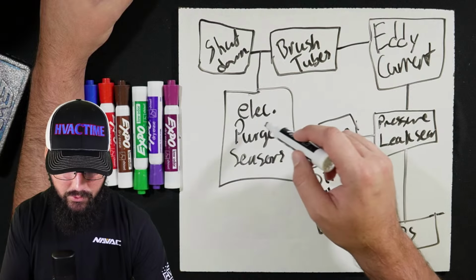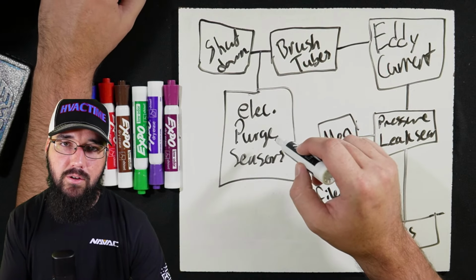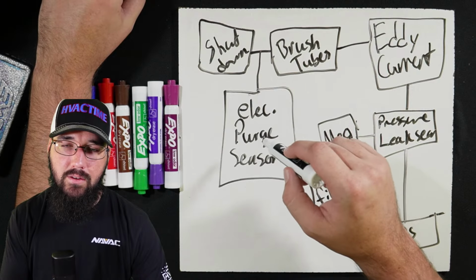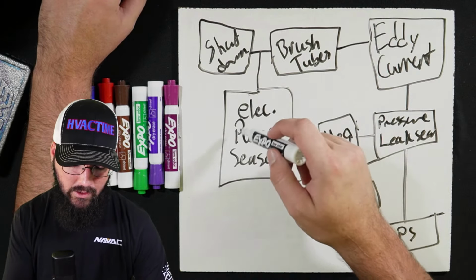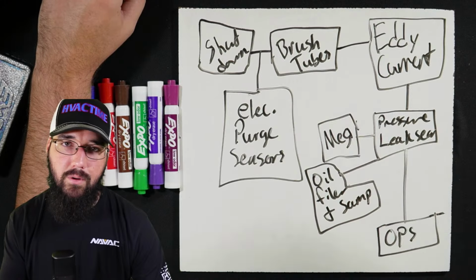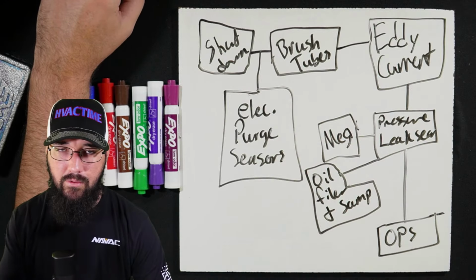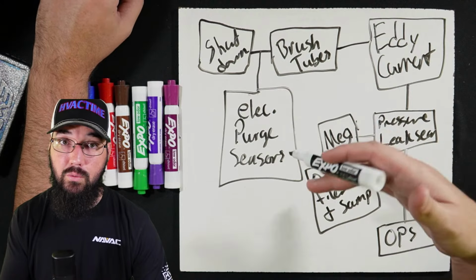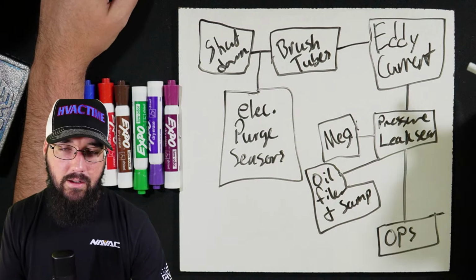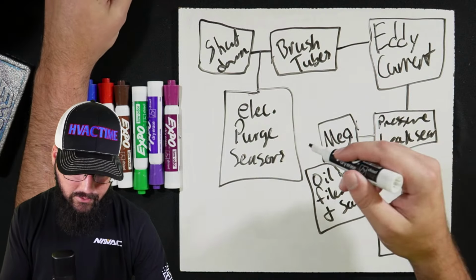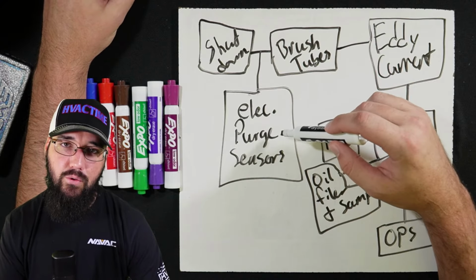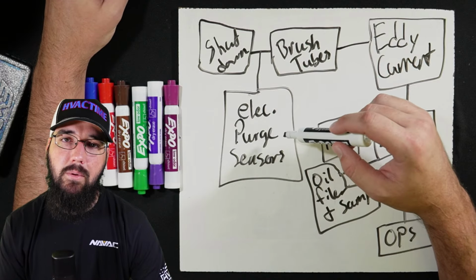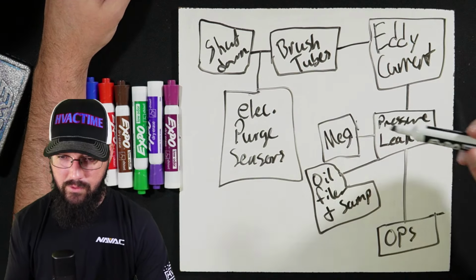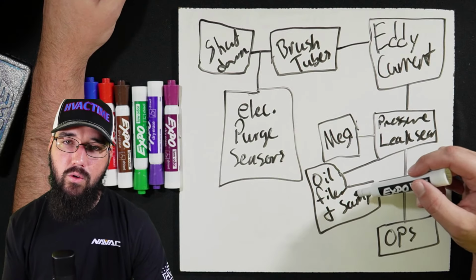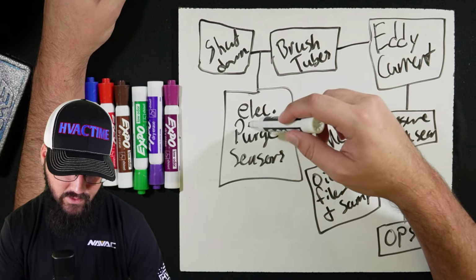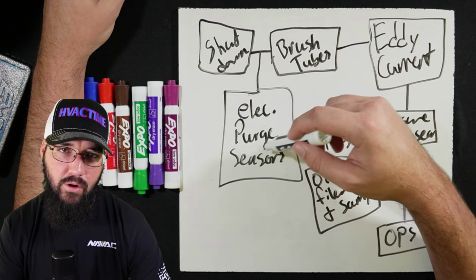One thing when you're doing this purge: make sure you pull an evacuation on the purge lines. I'm guilty of getting lazy and just opening the lines back up, letting the purge deal with the non-condensables that got introduced while changing the filter out. I get it, I've done it. But the more we can limit non-condensables, the better off we're going to be. That's why we do the oil filter while pressurized, and then we can do the purge while it's still in a vacuum.